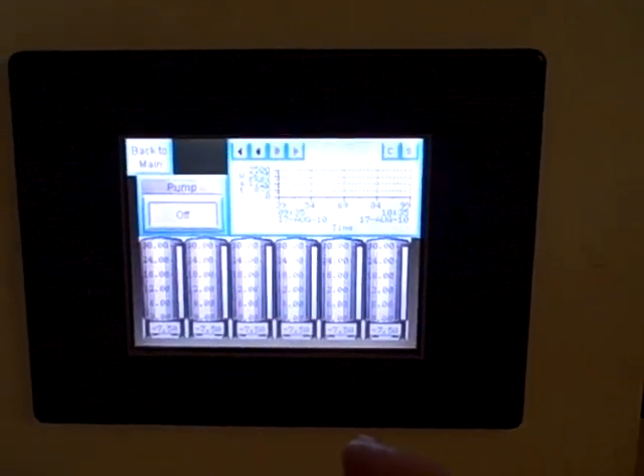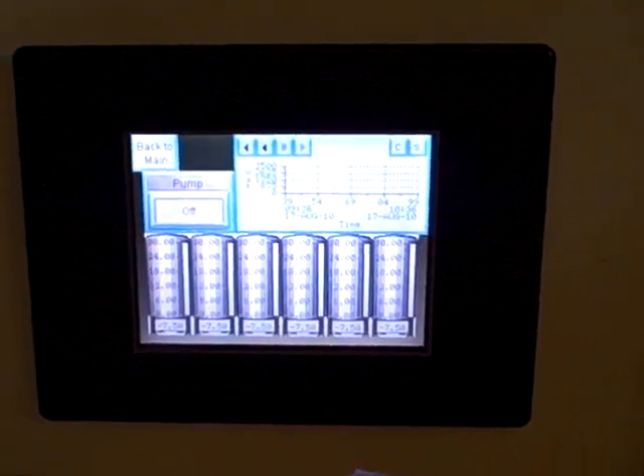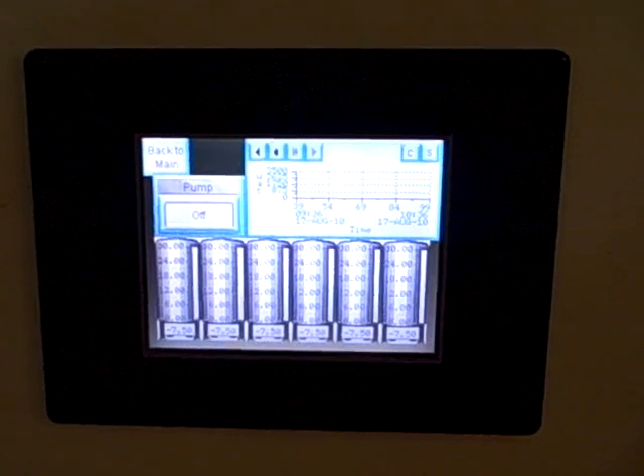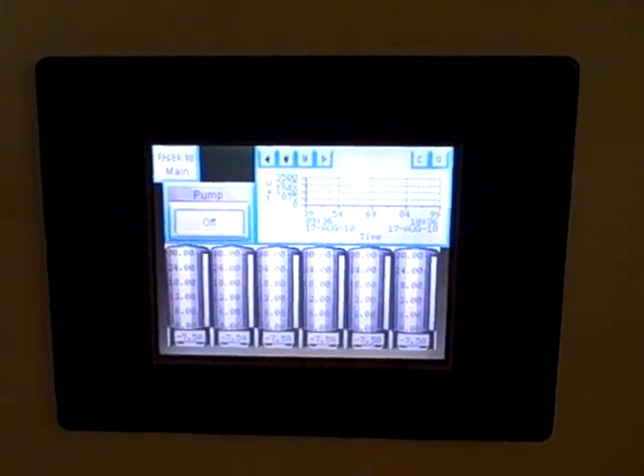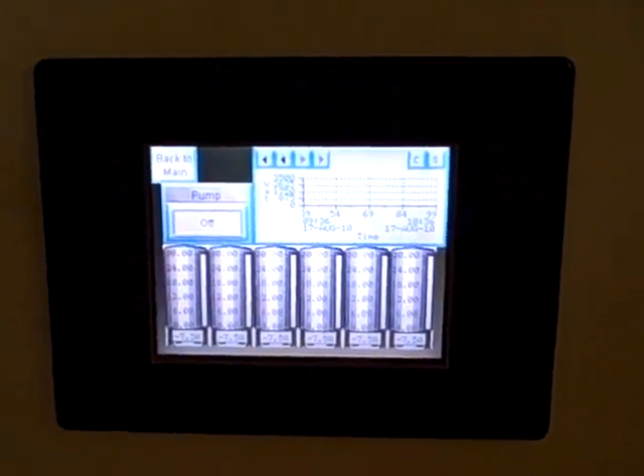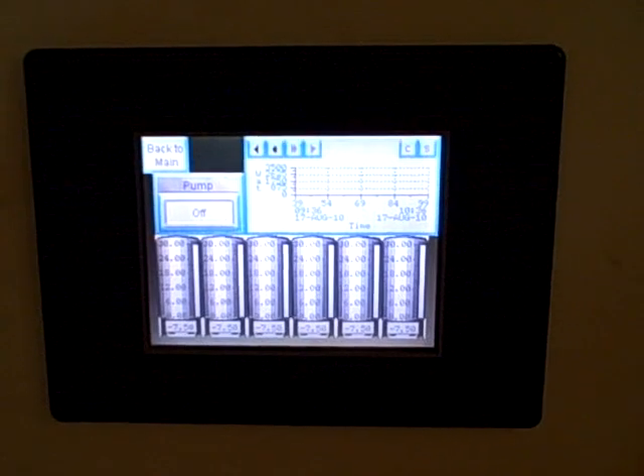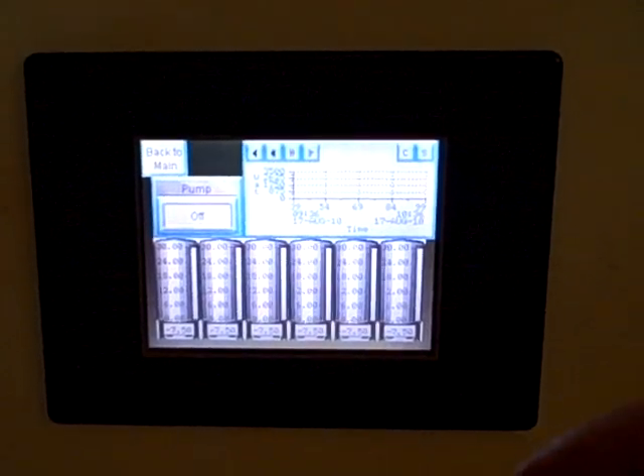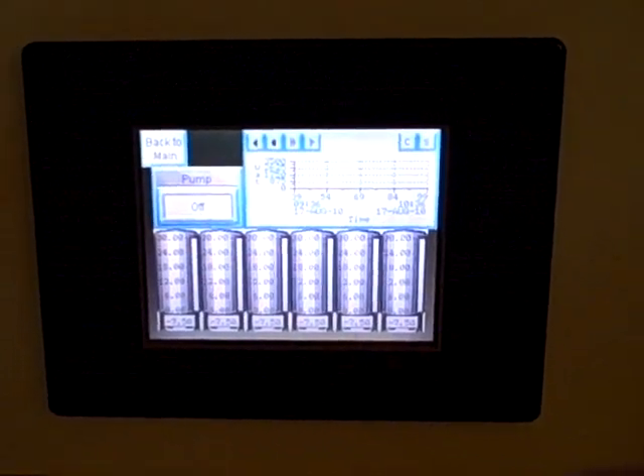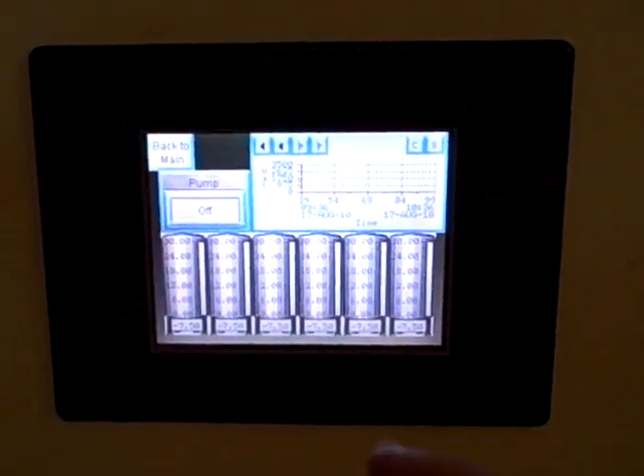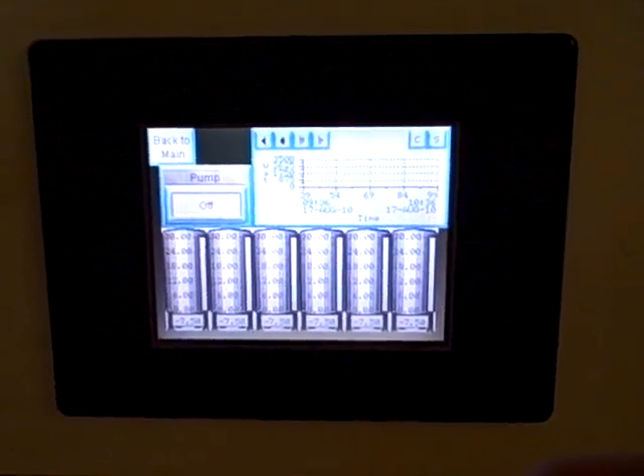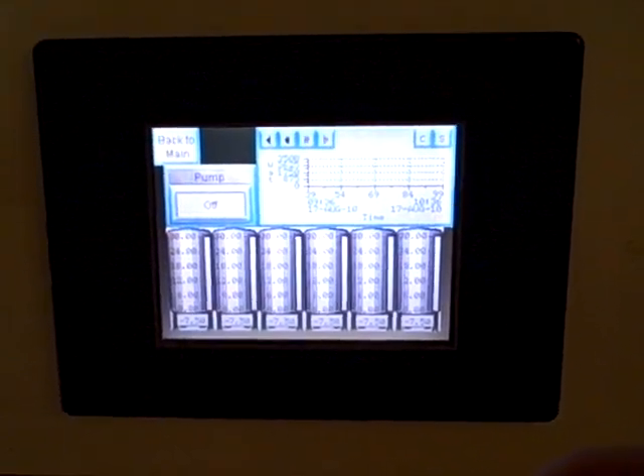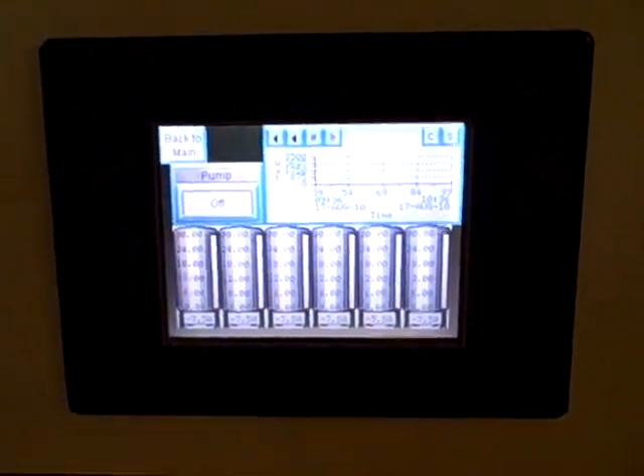So if you held the button down for one second, the pump would run for 100 seconds. If you held the button down for one and a half seconds, the pump would run for 150 seconds. And if you want to turn it off, you just briefly tap the button and that momentary actuation translates into 100 times that, which is usually just a few seconds and the pump shuts down.